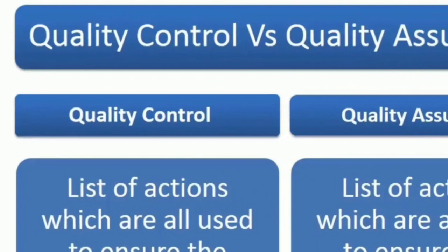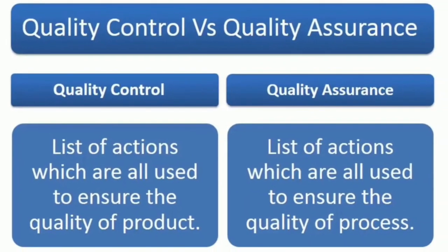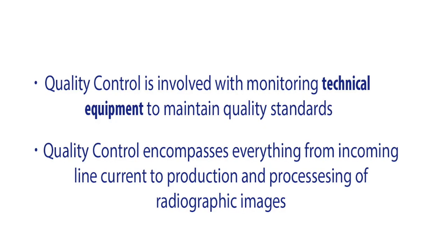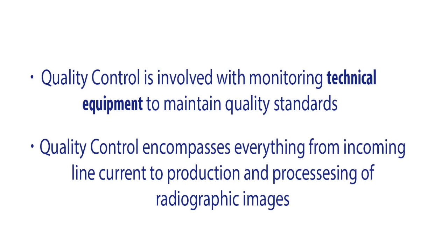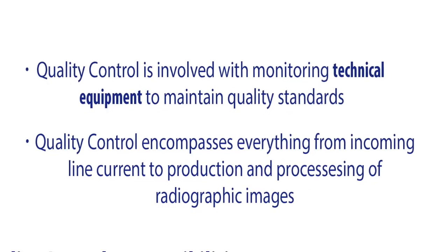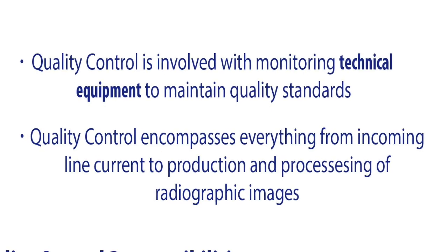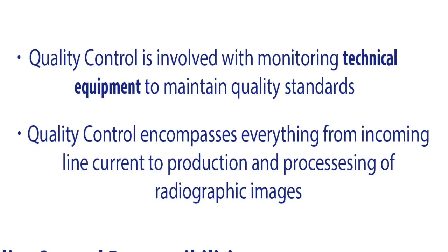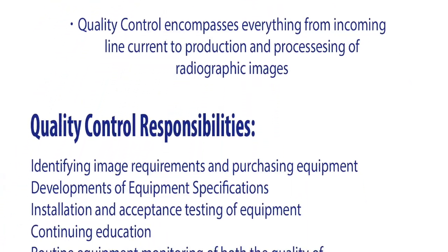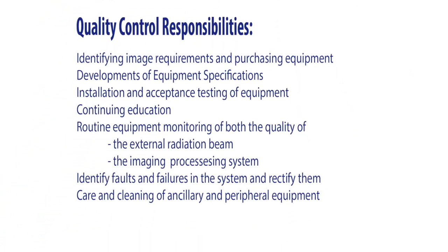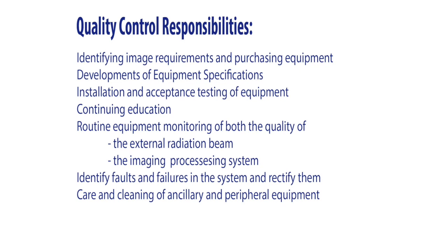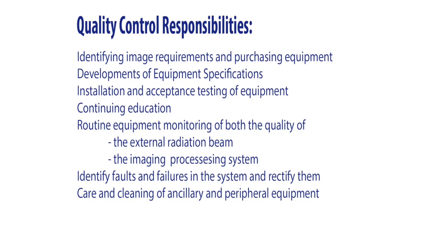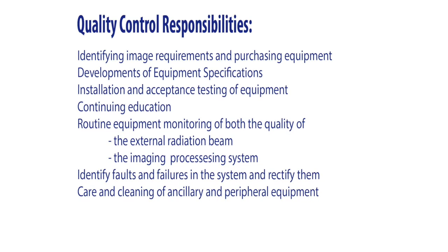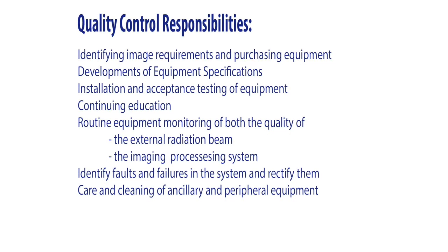Quality control refers to the regular intermittent technical testing of medical equipment and evaluation of image quality to ensure technical expectations are met. Quality control initiatives establish acceptable ranges and then maintain and improve on these set standards of what is acceptable in relation to technical aspects of radiologic imaging. They perform such tasks as routine monitoring of equipment parameters by acceptance testing and preventative maintenance, as well as establishing and implementing a protocol to take corrective action when these parameters are not met in order to rectify the issue. Included in this is the maintenance, repair, and testing of the facility where the equipment is being utilized.